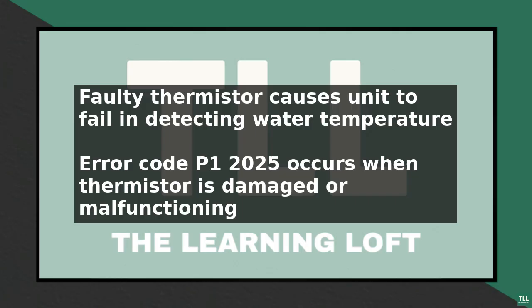To troubleshoot the issue, start by checking the thermistor for any signs of damage or corrosion. If the thermistor is damaged, it will need to be replaced. Next, check the wiring connections to ensure they are secure and not loose. Loose connections can cause the thermistor to malfunction, resulting in the error code.